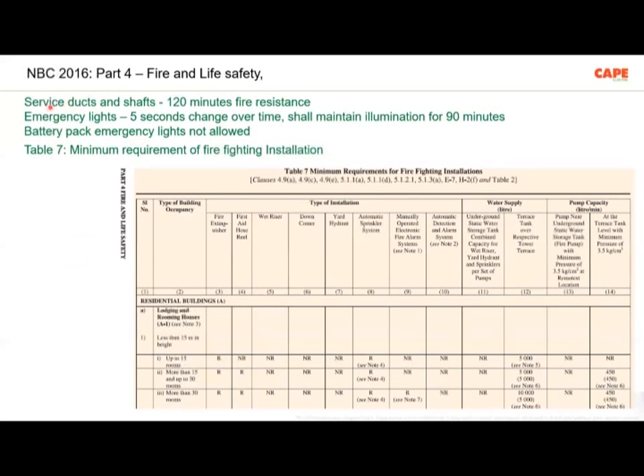If we look at the NBC, service ducts and shafts should be fire resistant for 120 minutes. The electrical installation for emergency services should have 120 minutes fire resistance. Whereas if we look at the IS732, the minimum requirement is 1 hour. But anyway, we have to follow the National Building Code. Emergency lights should switch over within 5 seconds. Battery packed emergency lights are not allowed. These are actually influencing the safety.